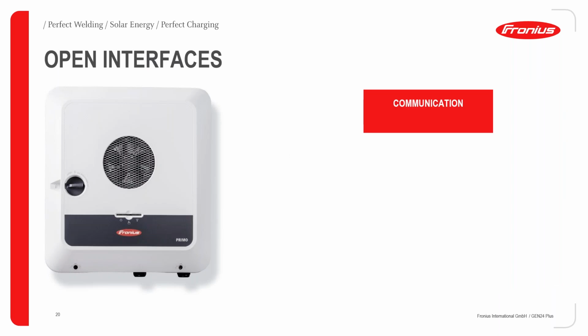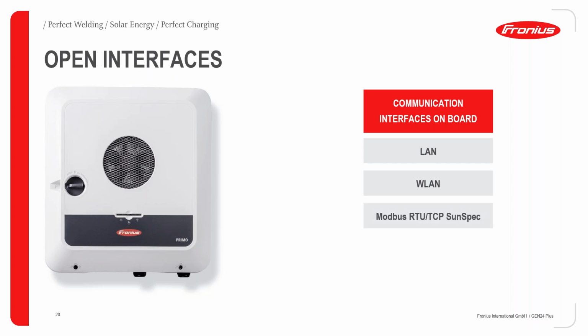Yeah, just to sum it up a little bit regarding the open interfaces, all the communication is of course on board as standard. LAN connection, Wi-Fi connection is of course possible. We have Modbus RTU for Fronius components, so if a battery would be connected like that, a smart meter, Ohmpilot, and so on. And also Modbus TCP connection is possible, so providing the data for a third-party unit, for example.